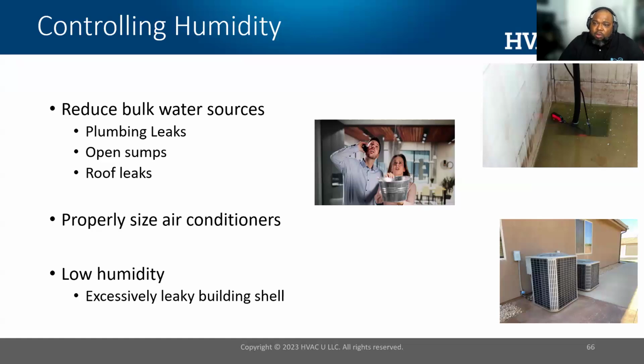To control humidity, you want to reduce bulk water sources such as plumbing leaks, open sumps, and roof leaks. You really want to size air conditioners properly, as they are designed to remove temperature and humidity from the air. If they're not sized appropriately, they won't control the moisture. You can be closer to that 60% relative humidity mark where you can start to get mold growth. Low humidity is also an issue, and at times like now, I live in Michigan here, and it's cooler.